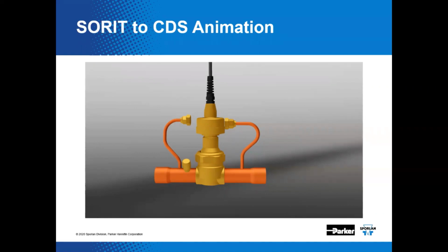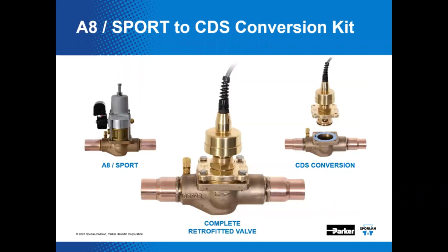Yeah. Discharge air temperatures are typically monitored by that EMS that we've mentioned multiple times now, and they may even be equipped with the logic to control the EEPRs. That would mean a complete EMS upgrade likely would not be required for you to do a retrofit like this. True. Neat thing is we've got these for a wide array of valves. The Refrigerating Specialties Sport to CDS kit is also available to retrofit that Sport valve to a CDS design.